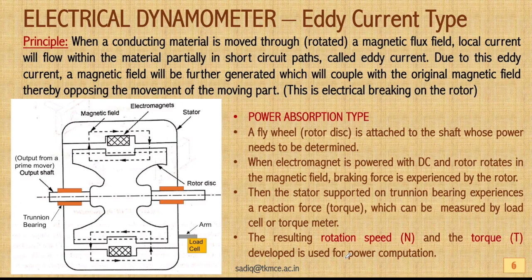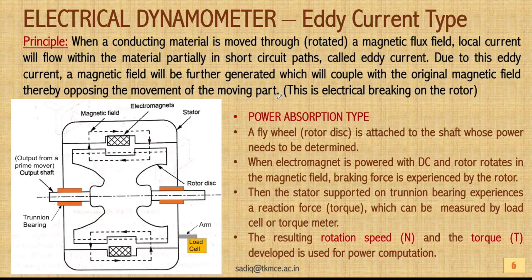The electrical dynamometer discussed here is the eddy current type, again a power absorption type. The principle is: when a conducting material is rotated in a magnetic flux field, local currents — called eddy currents — flow within the material in short circuit paths. This eddy current generates a magnetic field that couples with the original magnetic field, thereby opposing the movement of the rotor. This is called electrical braking on a rotor.